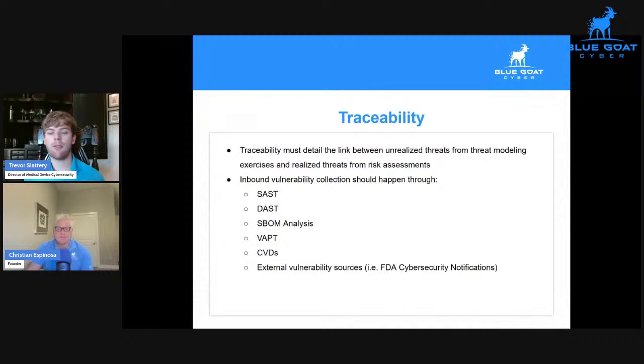So these different sources can also vary pretty heavily depending on the device. There can often be sources specifically for different components in the device. So identifying the manufacturer of a microcontroller and then subscribing to their security notifications can be a great way to get some external vulnerability collection in. If there's a vulnerability that pops up in that microcontroller or the manufacturer identifies a design problem, you'll be notified through that means, while it may not typically be notified through other medical device means.